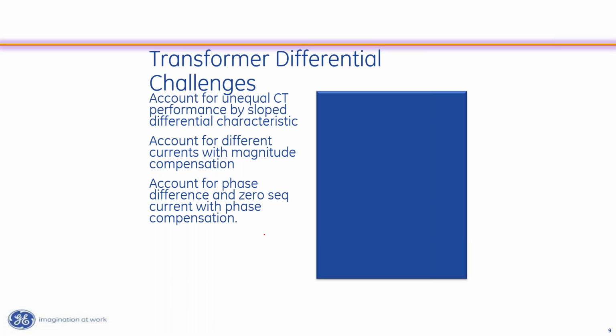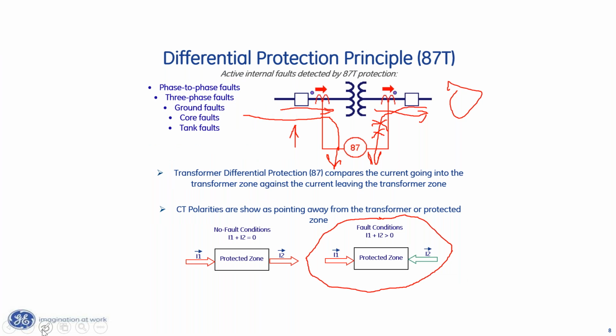Let me go backwards in time. Backwards is never a good direction to go, but we're going to go that way. And let's grab an eraser and erase some of this junk off of here so it's a little bit clearer. Let me get my pen back. So let's assume that I've got a fault right there. If I've got a fault right there, that looks like 10 per unit of current at 0 here, and that looks like 10 per unit at 180 degrees there.